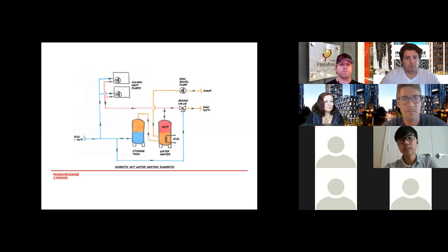Secondly was the temperature in the second storage tank, or the electric water heater. We set the electric resistance element to 120 degrees Fahrenheit, lower than the other storage tank. There's a reason for this: we didn't want to use the electric resistance element as the primary source of domestic hot water heating. Its sole purpose, besides redundancy, was to top up the domestic hot water recirculation when it experiences piping losses in the system.